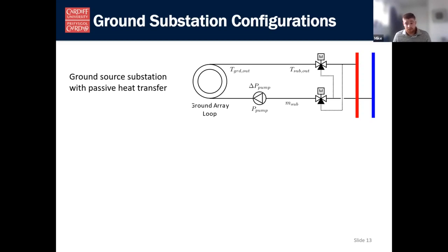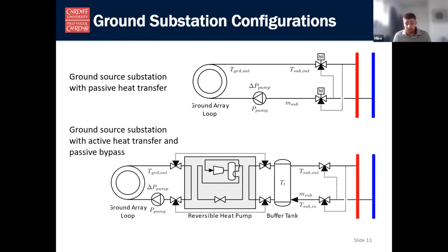If we want to fix the nominal temperature above that of the ground array, then we would need a heat pump to raise the temperature. And with that configuration, any heat rejection back to the ground can be achieved either through a bypass or by active cooling with the heat pump, depending on the relative temperatures between the ground and the network at the time.